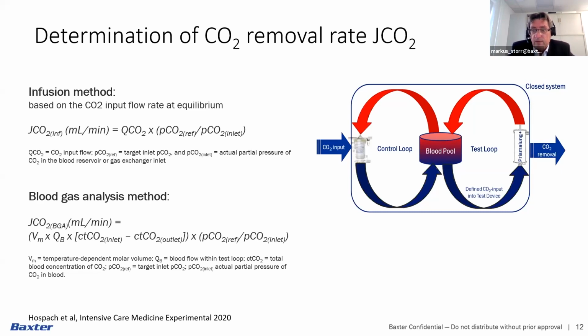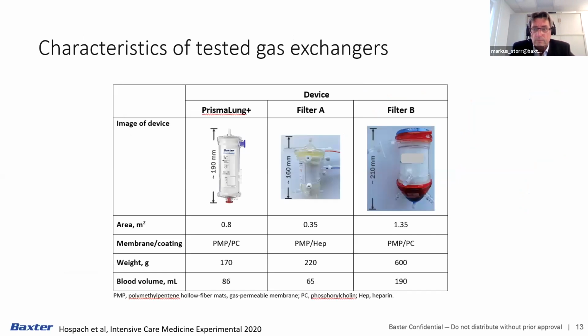To validate this method, we also determine the CO2 removal rate according to the second equation, what you see, which is based on blood gas analysis data. So together with the PRISMALUNG Plus device, we've tested two other ECCO2 removal devices, which have the same PMP hollow fiber membranes, but with 0.35 square meter and 1.35 square meter respectively, different total membrane surface area.